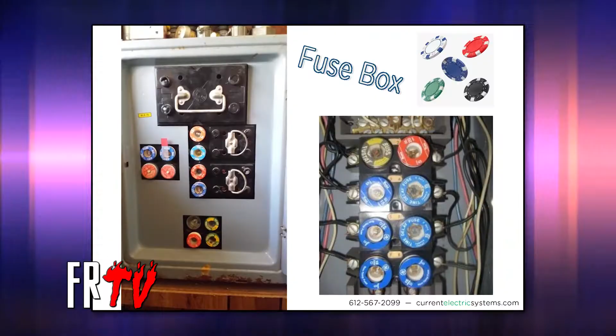And the first kind is you see like a fuse box where you have the little poker chip looking screw things, right? Yeah. A fuse does what it does well. It breaks a circuit on an overload or a short circuit very effectively and permanently until you replace the fuse, right? But 2 things, just the age of the equipment is one factor. But the second is that these blue ones are 15 amp and the orange one is 30 amp. And I've walked into homes where, well, I need more power, so I'll just put a 20 in. I'll put a 30 in. And you have wiring that's only good for 15 amps, fused at 30, that is a fire waiting to happen. You overload that, it will start a fire. So the fuse panels really need to go. That's just, we haven't had these in the homes for a long time.